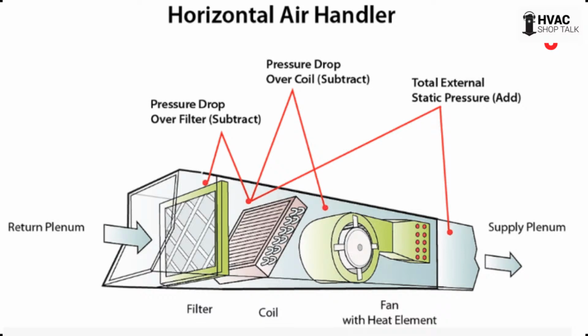Now you have to drill holes in the cabinets of stuff. When you drill holes in the cabinets, make sure you have a way to seal that hole, not just putting duct tape over it. Make it look professional. I know a lot of you are putting duct tape over the hole, like I've often done, so that's why I wanted to say that. I just want people to ask, hey, what's wrong with duct tape? My answer is nothing. There are little metal things you can stick in there, rubber grommets you can put in there, but duct tape will probably be the best thing because it'll stay stuck, especially in the attic, since the heat fuses the glue and it becomes one with the air handler. So duct tape is fine. It's approved here at Shop Talk, but that holds no value out there in the world.